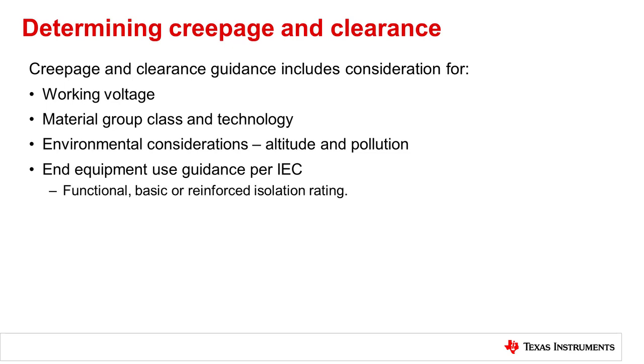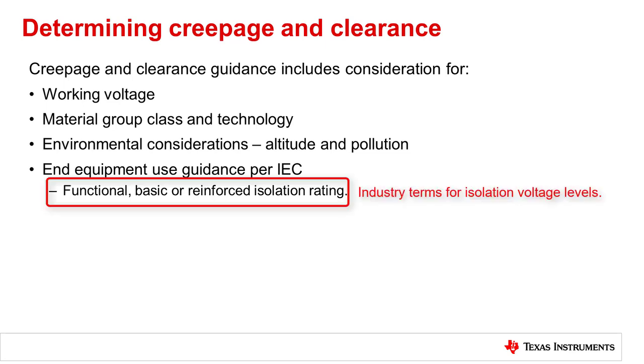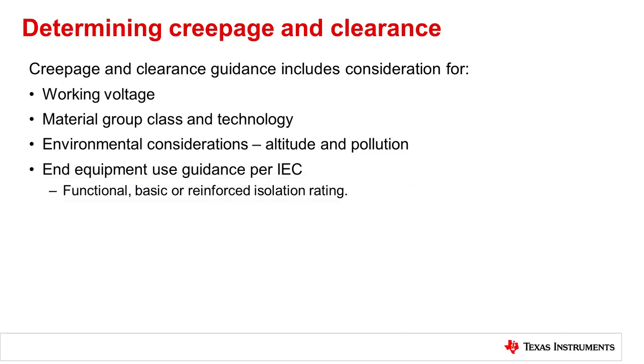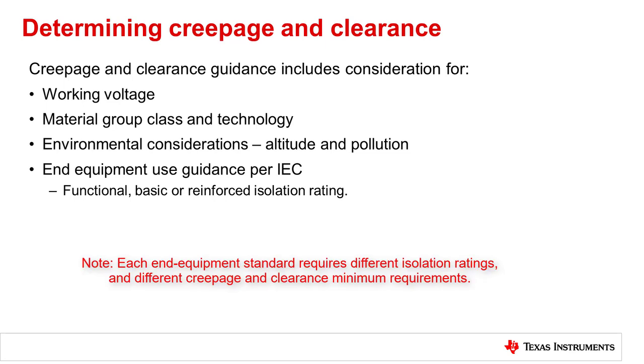The minimum distance for creepage and clearance will depend on whether the design requires functional, basic, or reinforced isolation ratings. These are the industry standard terms used to describe levels of voltage isolation performance and minimum safety requirements. The level of component isolation rating required is determined by the end equipment standards body — for example, the IEC standard for medical devices has different requirements than the standard used for test and measurement. Before you select a basic or reinforced isolator for your design, you will need to consult with the end equipment standard for rating. Let's do a brief review of the differences between functional, basic, and reinforced insulation ratings.